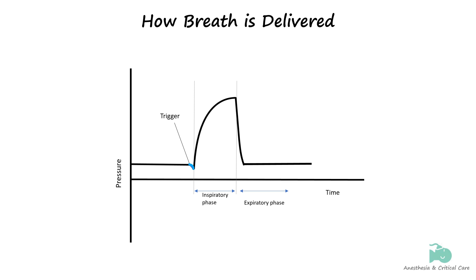After the breath starts, the machine delivers gas to the patient in a set pattern throughout inspiration, which is called the target variable. The two main target variables are a specific inspiratory flow rate or a pressure goal. The breath delivery stops when a certain amount of time has passed, or the ventilator senses a decrease in the patient's airflow. This is known as the cycle variable.